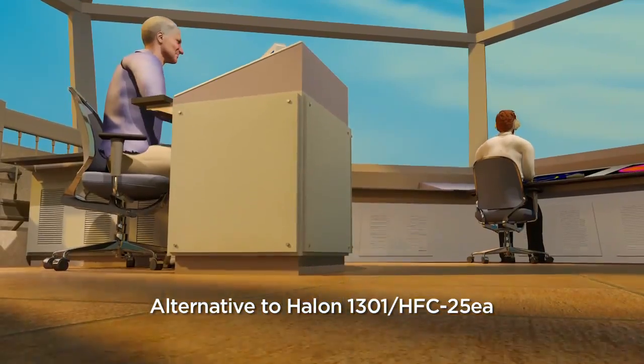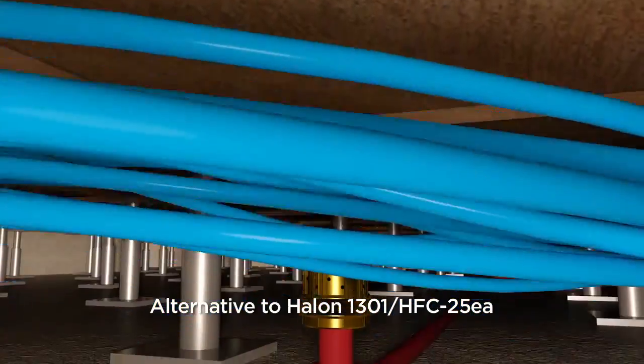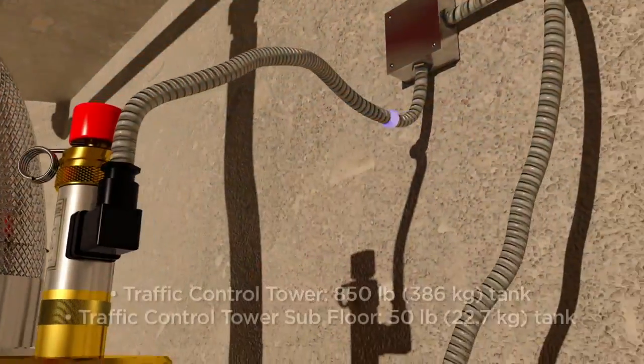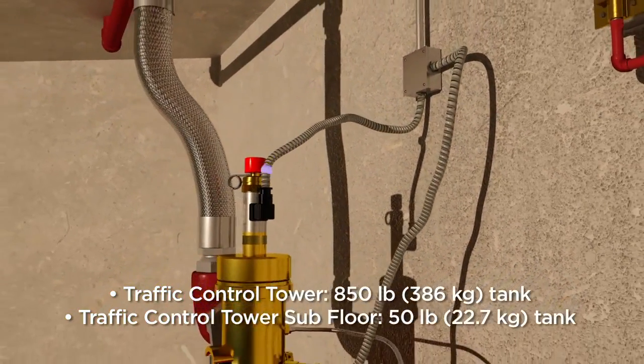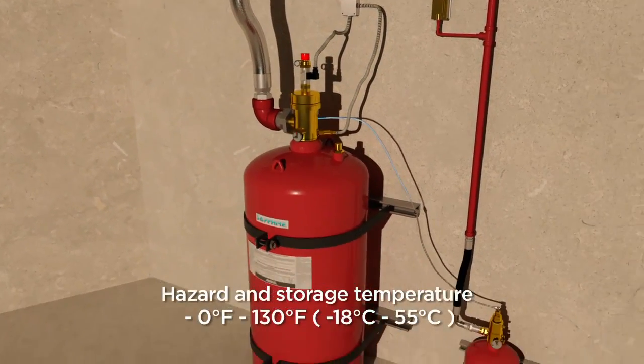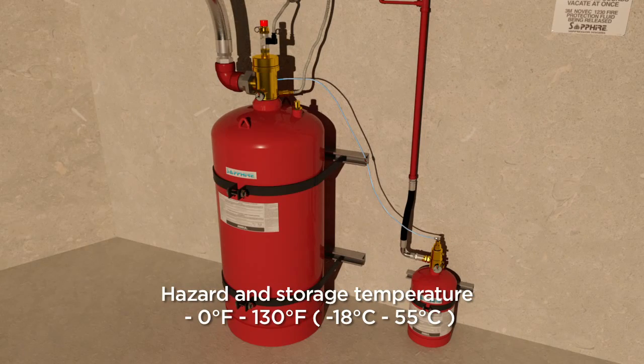The versatile Sapphire system can support the protection of multiple hazard zones, such as a main hazard area and subfloor. In multiple tank systems, the electric actuator opens the master valve. Additional tanks are actuated pneumatically through quarter-inch stainless steel hose and a pneumatic actuator installed on top of each valve.